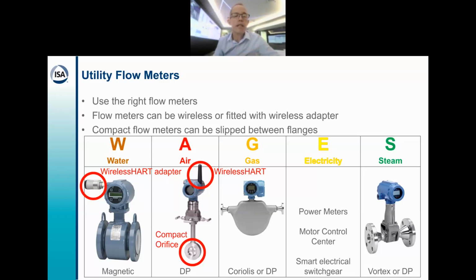Now, deploying sub-metering can be tricky because flow meters are mostly inline and therefore intrusive, meaning you must open a section of pipe to insert the flow meter. So although this can be a challenge, this doesn't mean you shouldn't do it, because a software solution without granular sub-metering is not helpful. Now, in a batch operated plant, you can install inline flow meters during the idle time between batches. But for a continuous plant, you will have to install inline flow meters during the next turnaround or other outages or shutdown. So plan for that now.